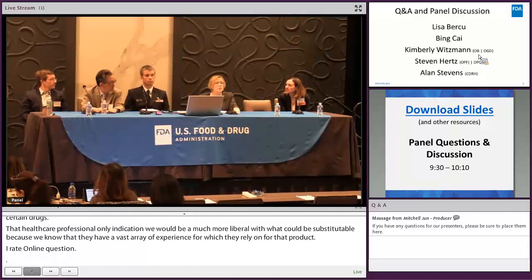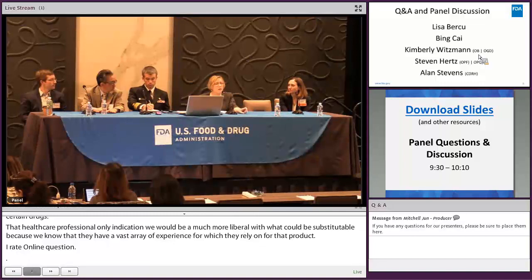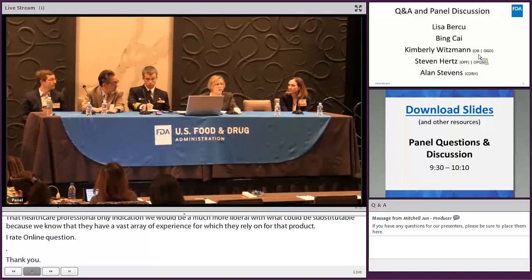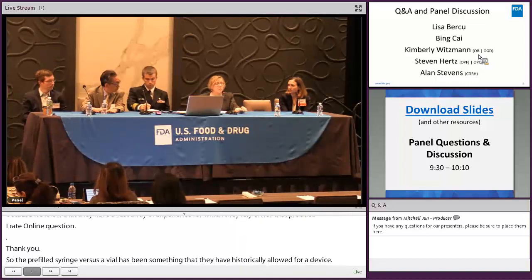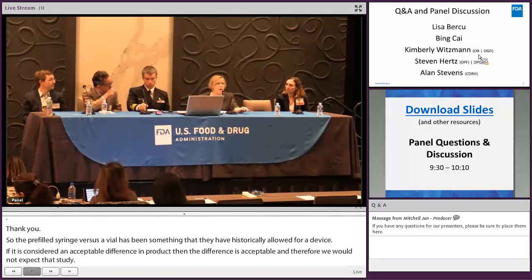Thanks. So the pre-filled syringe versus a vial has been something that FDA has historically allowed as an acceptable change for a device. If it's considered an acceptable difference in a product, then the difference is acceptable, and therefore we would not expect a comparative use human factor study. Let me go back a little bit because it seems like there's a lot of confusion about comparative use human factor studies and when you need or don't need them.